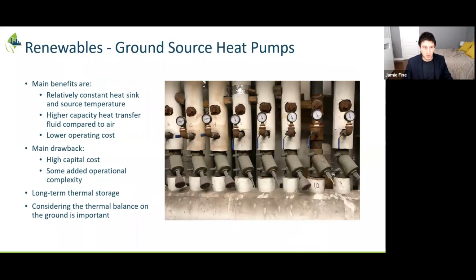The tubes can be buried horizontally or vertically; if vertical, they go several hundred meters into the ground usually. You put fluid in the ground, cold fluid at maybe 2 degrees Celsius, and it comes back out, at least in Ontario, around 10 degrees Celsius. That's what you'd do during the winter.